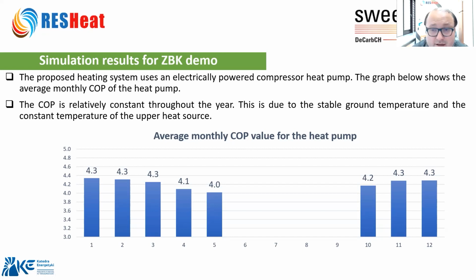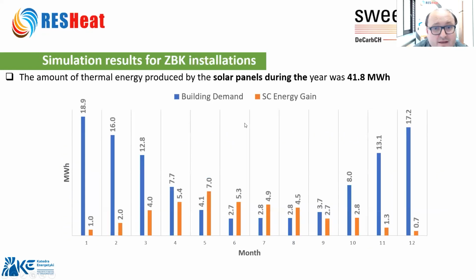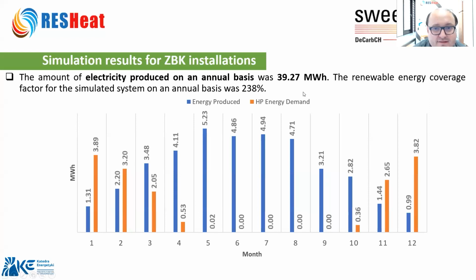Our simulation shows that it's possible to achieve a yearly average heat pump COP over 4, which is quite good for us, and we are able to deliver about 42 megawatt hours of heating from Suntrack solar panels, with the remaining heat delivered by the heat pump.